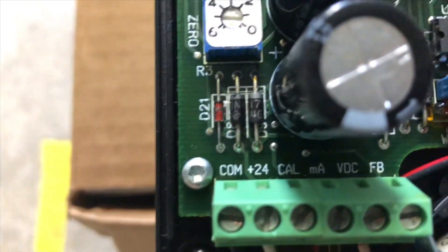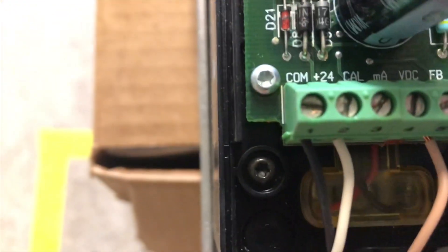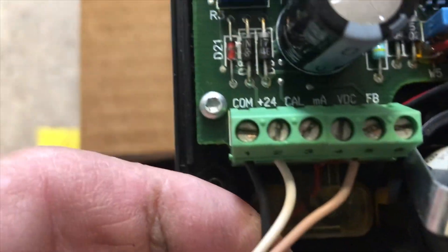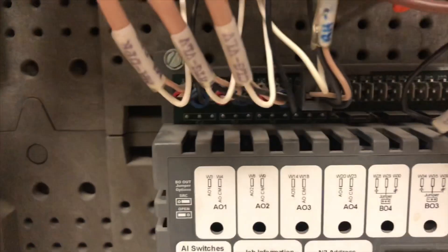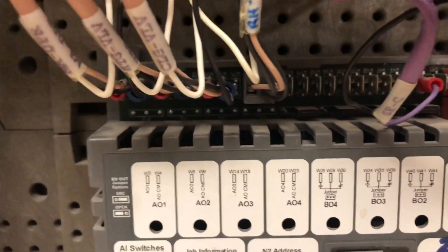So when you're trying to figure out your wiring, if you have DC on any of your wires, that's going to be your control wire. And you can always trace it back to your controller. If it's well labeled like this one is, we can go back to the board and figure out what wires what.